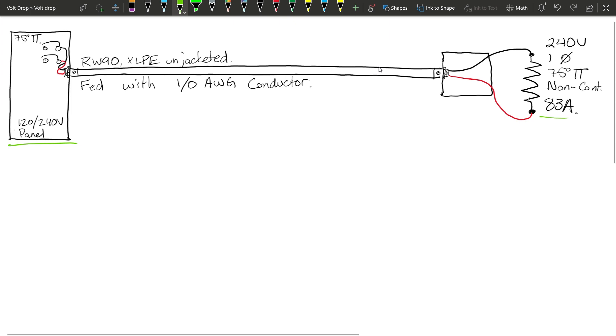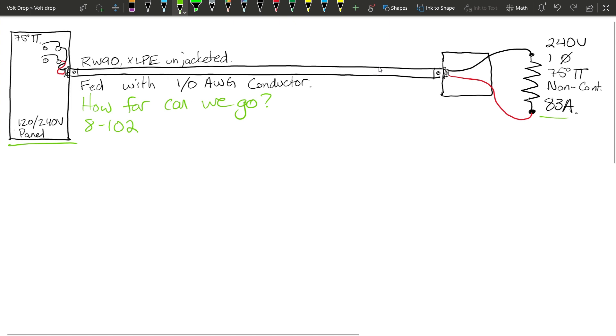What we want to determine is how far we can go given this information. We have a 1-aught gauge conductor feeding an 83 amp load with a 240 volt supply. The first place to look is rule 8-102, which tells us that a branch circuit is allowed up to a 3% volt drop. According to the definitions section, the branch circuit runs from the final overcurrent device to the point of utilization.